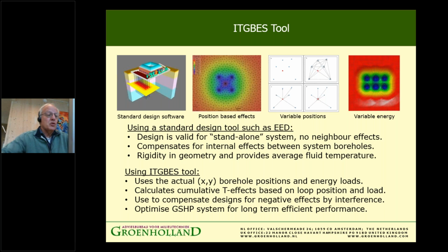If you use the ITGBES tool, it uses the actual X and Y borehole positions and energy loads, the realistic positions, and calculates the cumulative temperature effects based on loop position and energy load on that loop. Have you got more heating? More cooling? A larger heat pump? Do you extract more kilowatts?